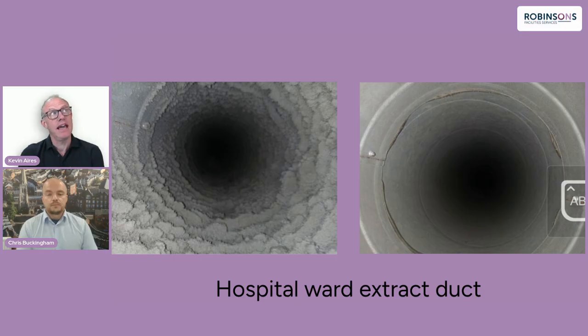Lovely, so I guess that's quite interesting. So what you were saying about the in and the out - I guess once you've had a clean, both on the in and the out, then you get a baseline, because you may not have had this cleaned for a while since it's been outside. Once you've had that first clean, you can start to see, is it building up? Because looking at this, we don't know - is this like one week, is this 10 years, has it never been cleaned? So after you look at it over a year, you can see what's coming in, what's going out, and get a sense of whether you're doing the right things here. Because if you're getting a load of build-up on the way in, you might need more filtration or something to stop it even getting into the duct, presumably.